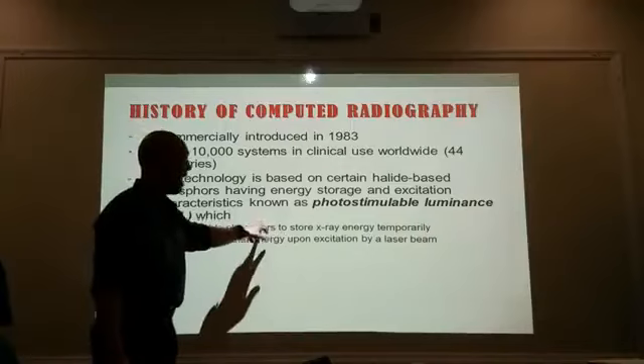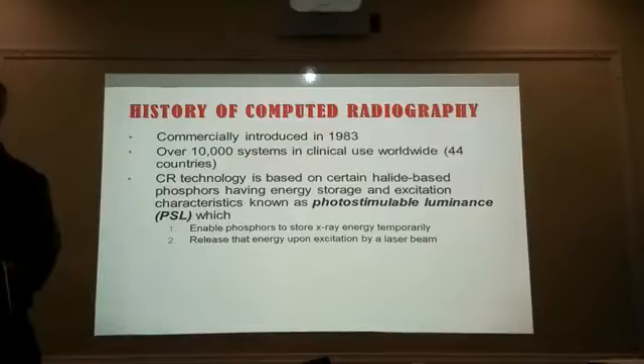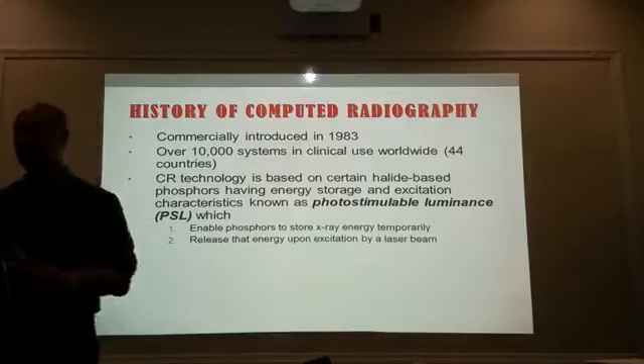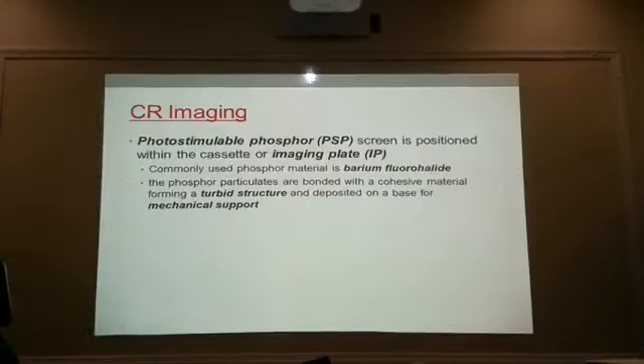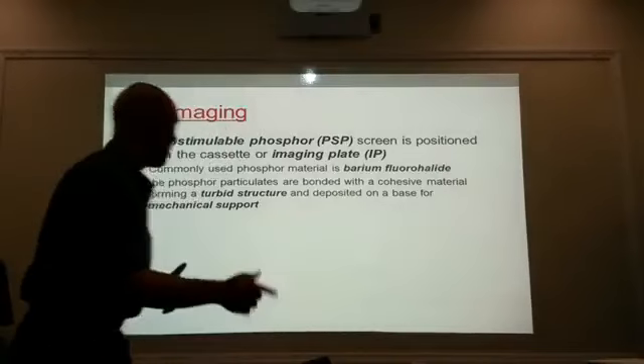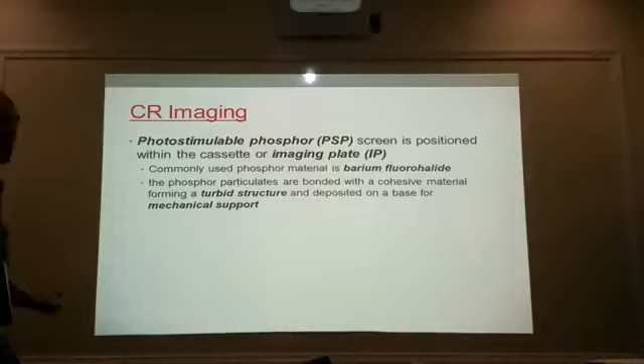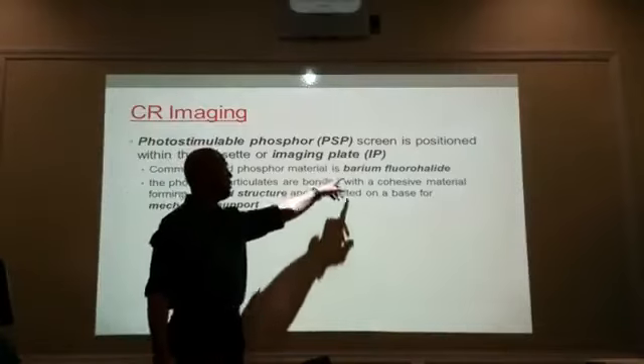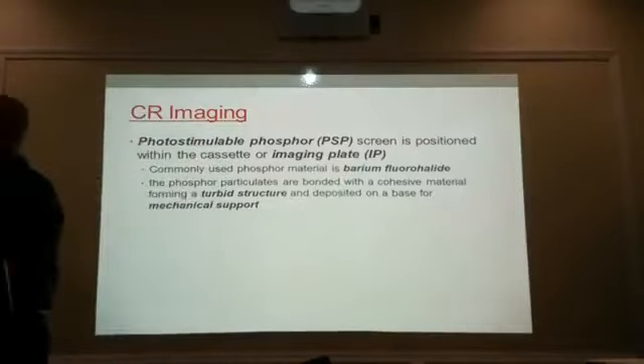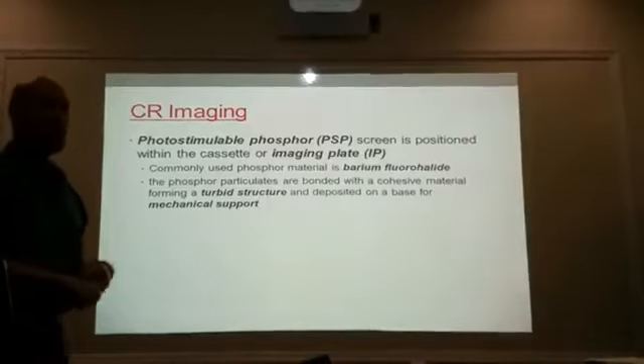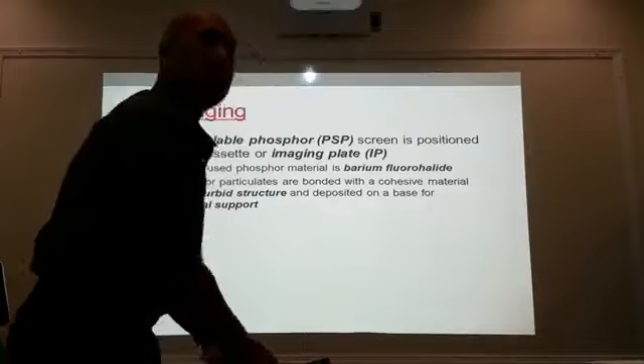These crystals have characteristics known as PSL, which allows the crystals to store the x-ray energy until they're scanned at a later time. The PSP screen is positioned within the cassette or the imaging plate. The commonly used phosphor is known as barium fluorohalide. Instead of your silver halide crystals in your film's emulsion, now we have barium fluorohalide within the turbid structure of the PSP screen. Turbid just means muddy — the emulsion is gelatin-like, the PSP is mud-like.